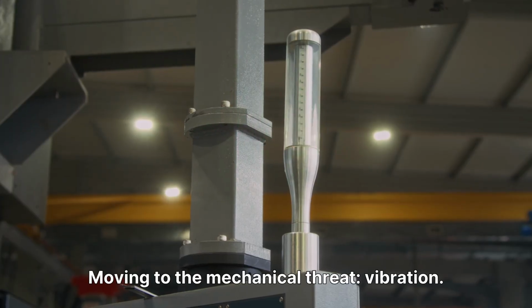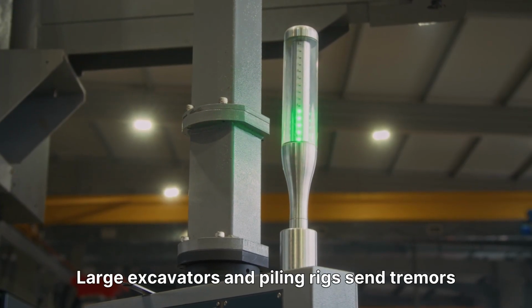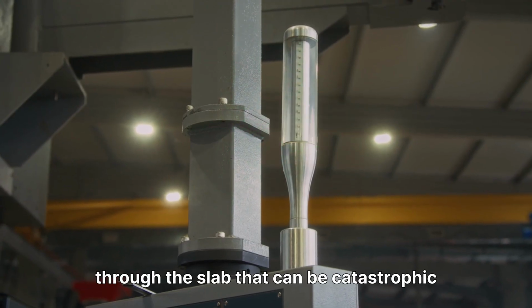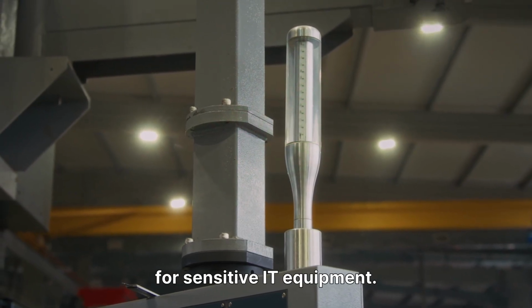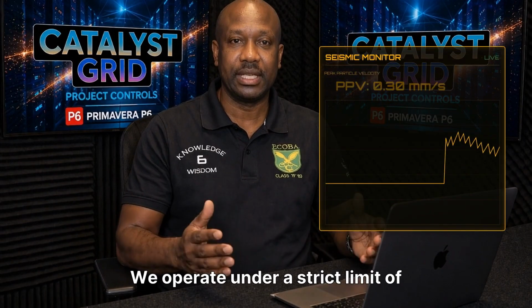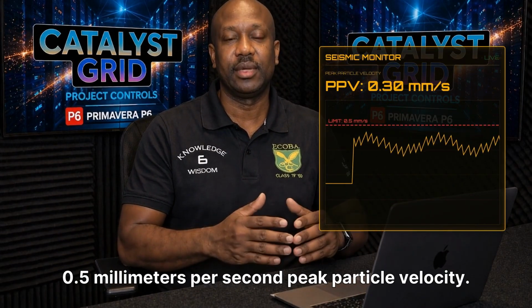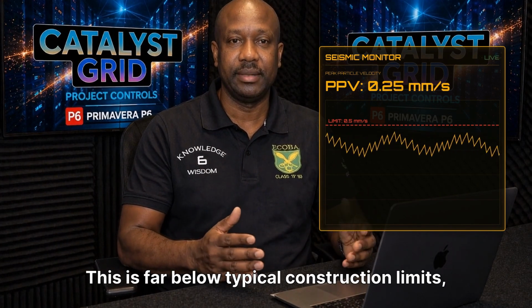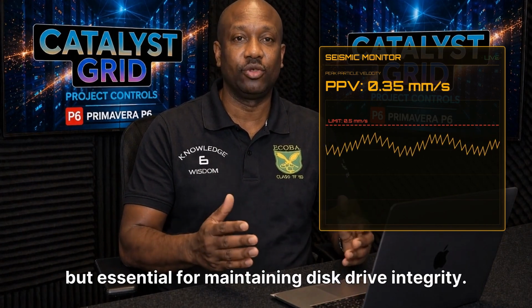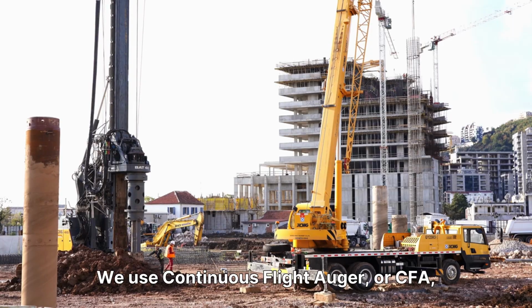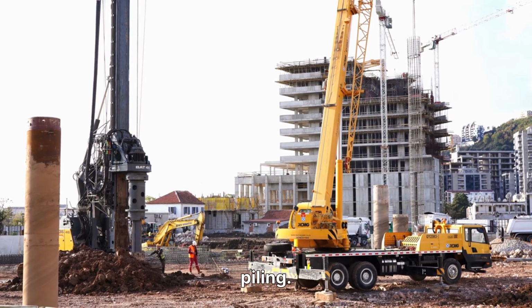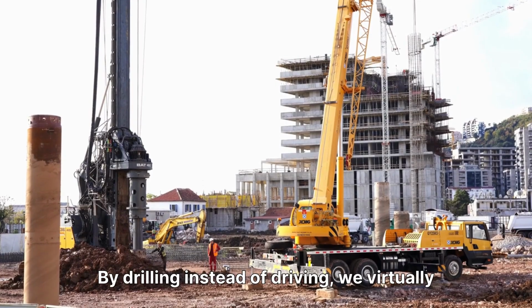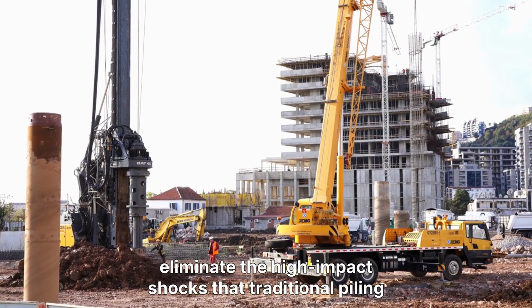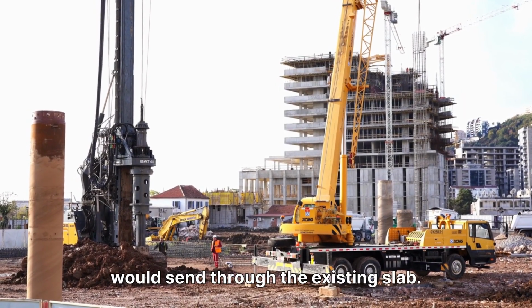Moving to the mechanical threat, vibration. Large excavators and piling rigs send tremors through the slab that can be catastrophic for sensitive IT equipment. We operate under a strict limit of 0.5 millimeters per second peak particle velocity. This is far below typical construction limits, but essential for maintaining disk drive integrity. We use continuous flight auger, or CFA, piling. By drilling instead of driving, we virtually eliminate the high-impact shocks that traditional piling would send through the existing slab.